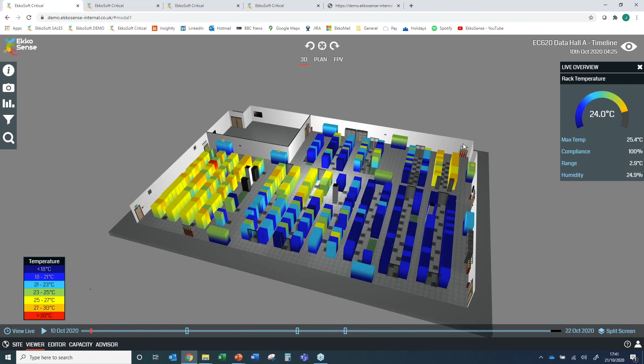The next thing I wanted to show you is the live information from the site, focusing on cooling capacity and cooling utilization. Very unique to EkkoSense, we have a sensor or range of sensors called EkkoAir, which go in each of the cooling devices on site, whether downflows, upflows, or air handling units of different types. It doesn't matter what cooling system or medium you use - we have sensors that universally pick up, and uniquely to us, actually pick up live cooling duty, telling us how much cooling an air conditioning unit is actually delivering.